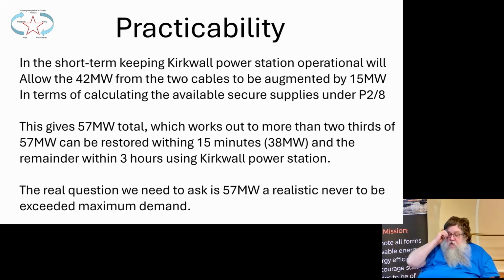So I've put in the short term, keeping Kirkwall Power Station operational will allow the 42 megawatts on the 2 cables to be augmented by 15 megawatts in terms of calculating the available secure supplies under P2/8. So it gives us 57 megawatts, a lot more than 42. It's a significant load, which we could argue, and we can talk about it in the discussion, whether we're going to get there. It works out to more than two-thirds of 57 megawatts can be restored within 15 minutes, 38 megawatts, by using the 2 cables, and the remainder within 3 hours using Kirkwall Power Station.